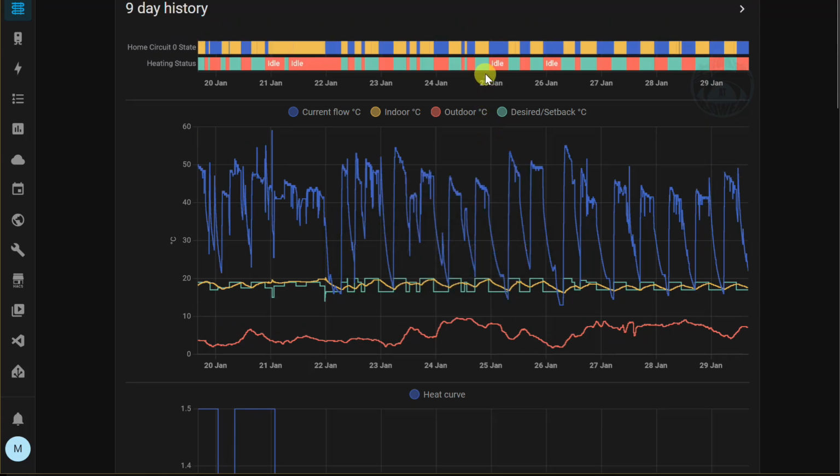And I can tell that because I've got this field called heating circuit. And here you can see it's heating and it's in line with the peak, and it's in line with the desired peak. That's during the timer. But now when it's outside of the timer, so this area over here, if I go back up this little portion, the status is saying idle and the blue is saying standby, and that means the boiler is off.